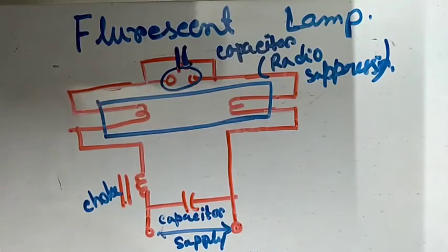When the supply is switched on, the current flows through the choke, the starter heater and the electrodes. The heater coil raises the temperature of the bimetal contacts and they separate. Thereby, the current through the choke is interrupted, and the consequent voltage pulse of approximately 1000 volts causes the tube to strike. Once the tube strikes, the tube current flows through the starter heater and the bimetal contacts remain open.